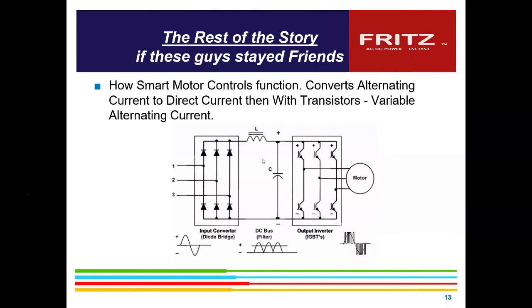There also are, if you do have fixed speed machines, now soft start devices which will do the soft start, and they just clip the waveform and improve the power factor and make the motor run more efficiently when you need fixed speed machines. There aren't as many incentives for that, but it definitely is a way.